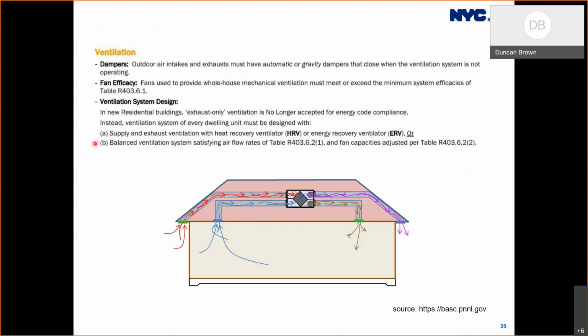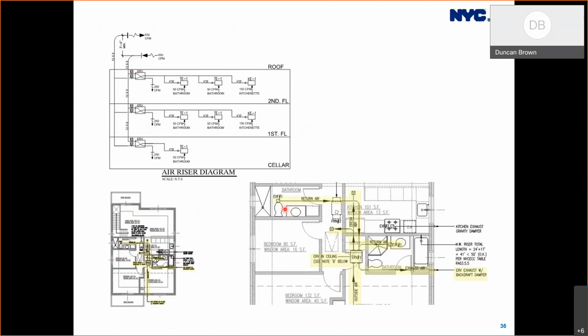So what's the difference between an HRV and an ERV? HRVs and ERVs are heat exchangers that take heat from stale exhaust air and use it to preheat incoming air. This saves on the energy and expense required to bring up the incoming fresh air to the required indoor temperature. So the primary difference between the two is that an HRV transfers heat, while an ERV transfers both heat and moisture.